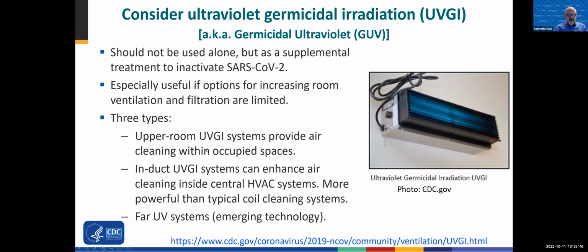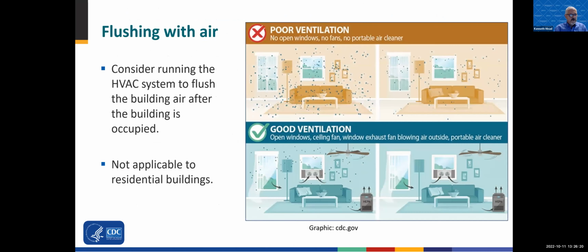We have a recommendation to consider using ultraviolet germicidal irradiation, sometimes called germicidal ultraviolet. It should not be used alone. It's a supplemental treatment to inactivate SARS-CoV-2 that's in the air. It's especially useful if options for increasing your room ventilation and filtration are limited. There are three basic types. Right now, CDC is putting more emphasis on using upper room systems and in-duct systems. Far UV systems are an emerging technology. And again, Dr. Martin is going to talk more about that. Steve is really CDC's UVGI principal expert, and he'll talk about that in his section of the presentation.